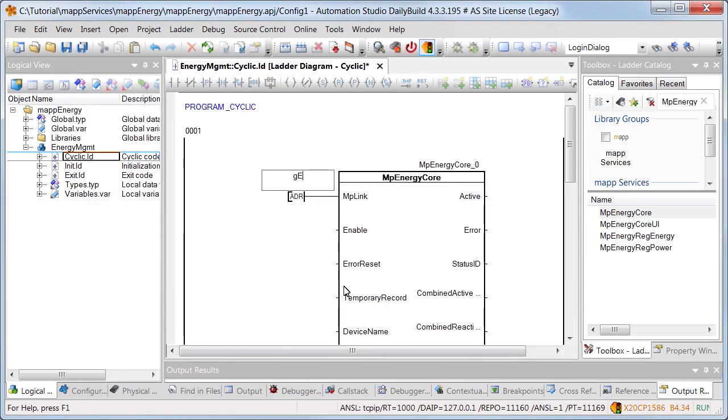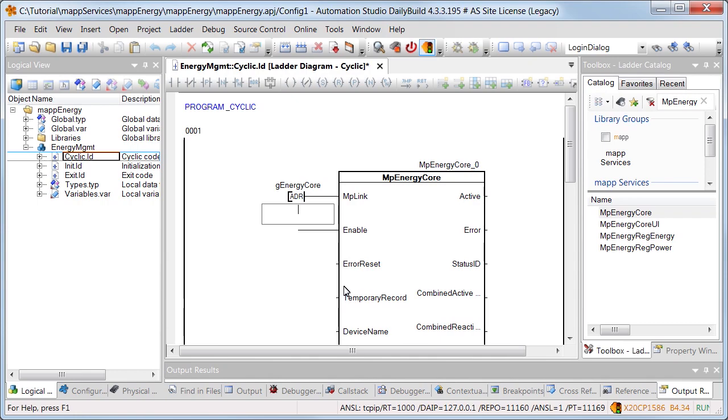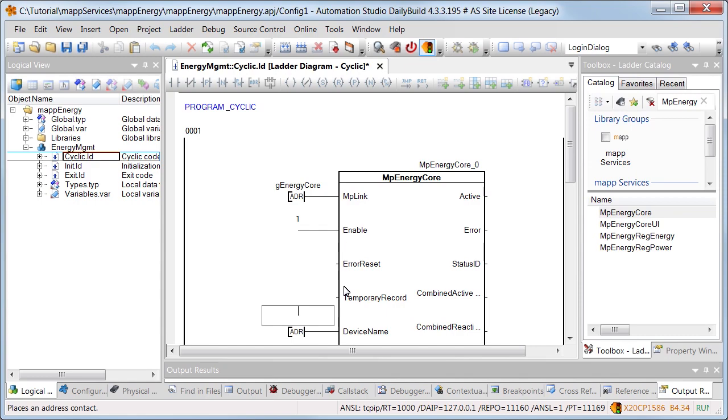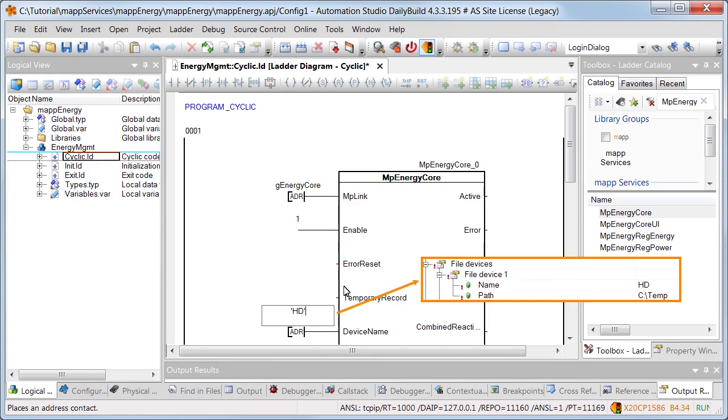Using input MP link, we establish a connection to the configuration we created earlier named G energy core. The function block is enabled using input enable. In order to save the energy data, a data storage device must be defined. This was previously defined in the hardware configuration and called HD.